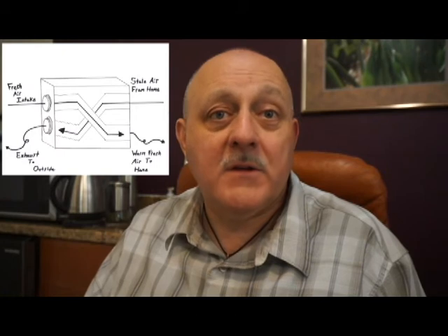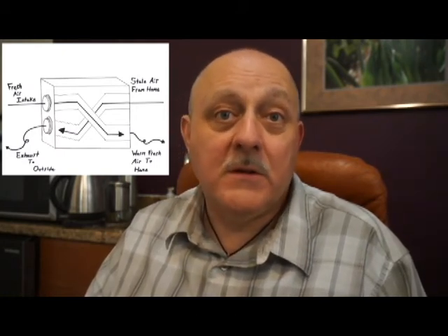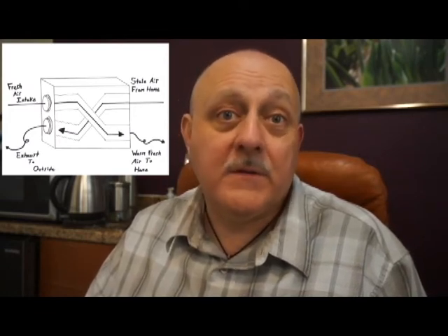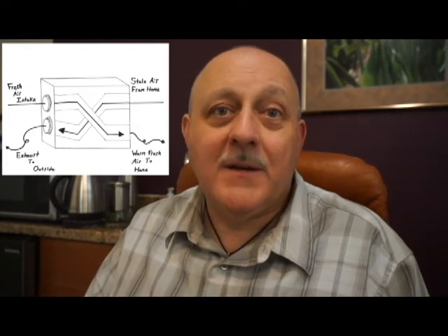And quite frankly, it really should be fixed in a better way than this first cost only stopgap measure of closing the fresh air. So there's something called an air-to-air heat exchanger, which will substantially reduce the problem of bringing in super hot air to cool when it's July and August. Well, we really have 10 hot months out of the year, 10 months where you might be air conditioning in Vegas. But regardless of what your weather environment is, getting a percentage of fresh air into your building is necessary for general good indoor air quality.